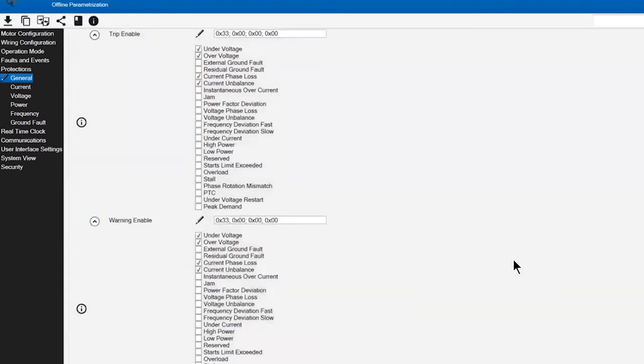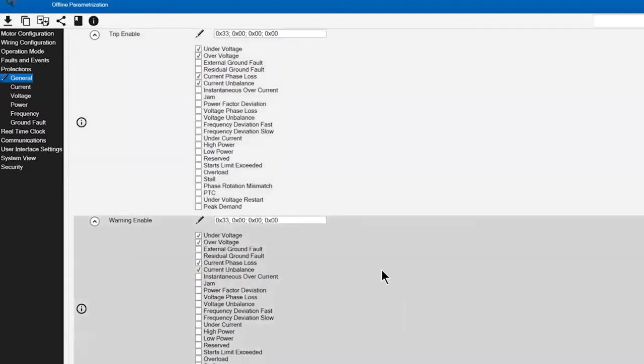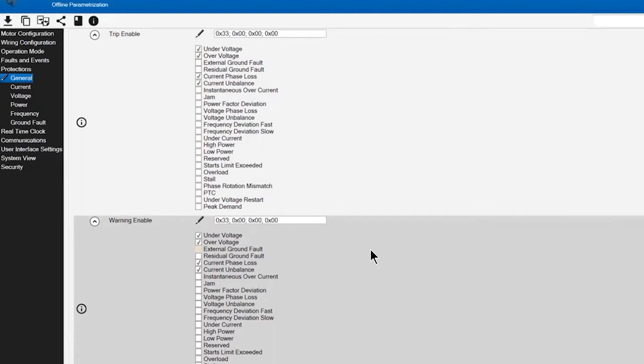Next, I'm going to go into the warning section. I'm going to utilize those same features—the under voltage, over voltage, current phase loss, and current unbalance—to set a warning point that gives me an indication prior to going to a trip event. It would alert me that conditions are not normal.